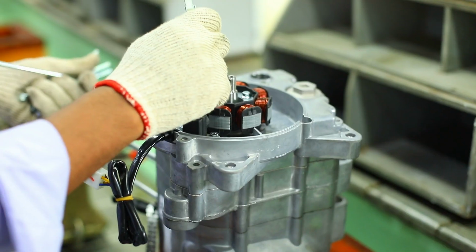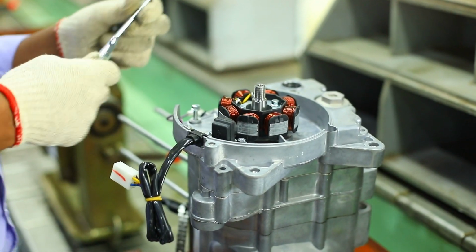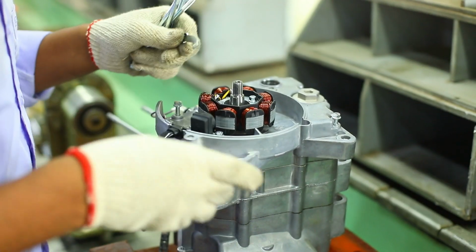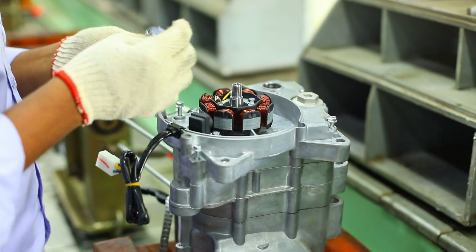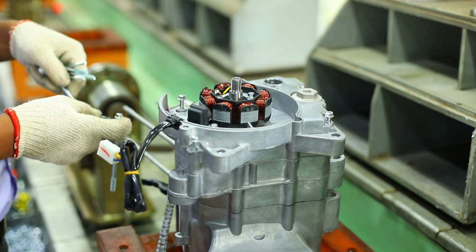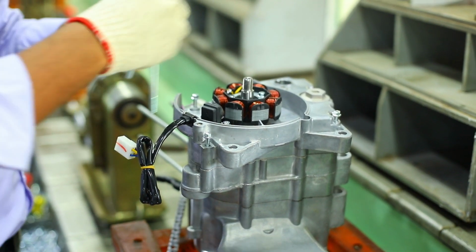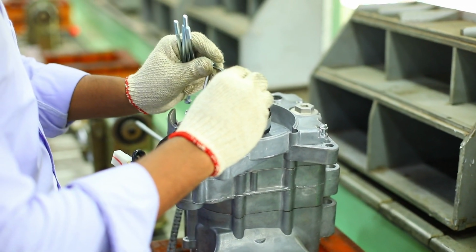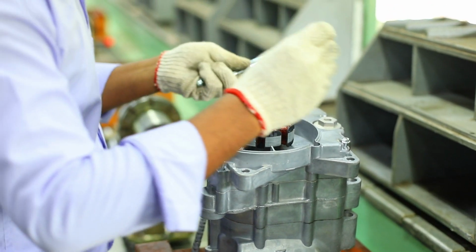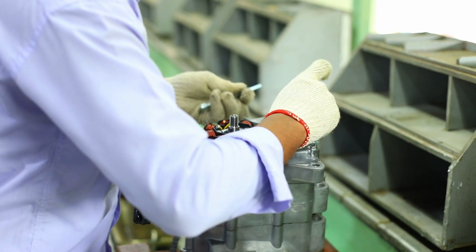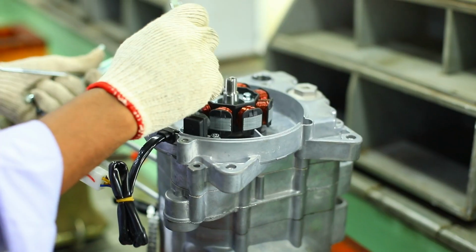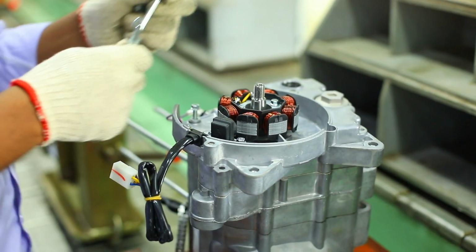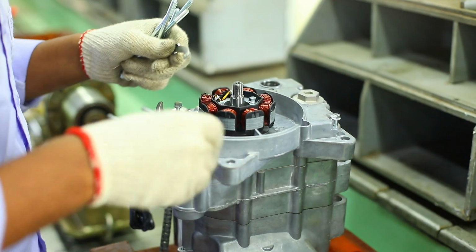Aluminum is a popular choice for the rotor bars because it's lightweight and has good conductivity. But copper and other alloys are also used, depending on the motor's requirements. And the source mentioned different types of squirrel cage rotors, right? What are the key differences? The main distinction is in how those rotor bars are attached to the end rings. In a welded rotor, the bars are individually welded to those end rings.